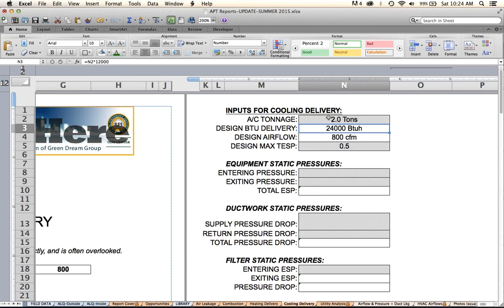So design BTU delivery is this number, 2 times 12,000, because there's 12,000 BTUs per ton. And the design airflow is 2 times 400 CFM, because there's 400 CFM per ton of cooling, and that's a really static number. That doesn't really change. If you're in the desert or you're in Florida, that might go up or down by, you know, 10, 15%, something like that, but it's not going to vary too much.